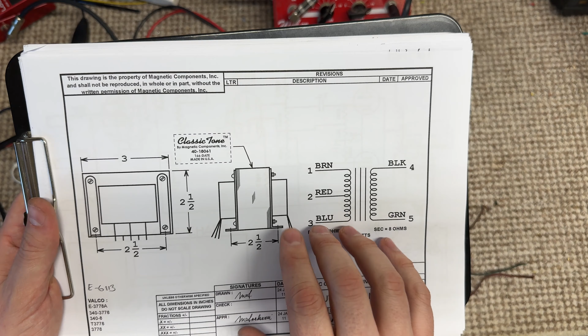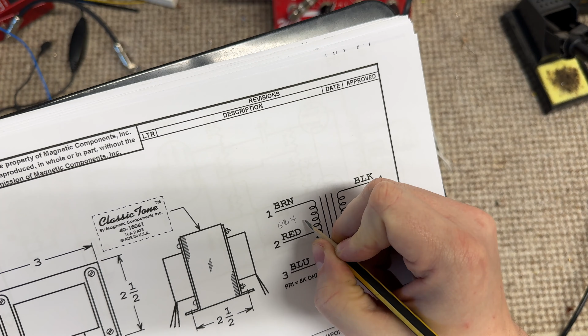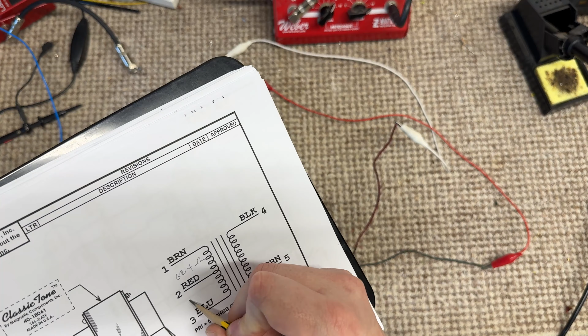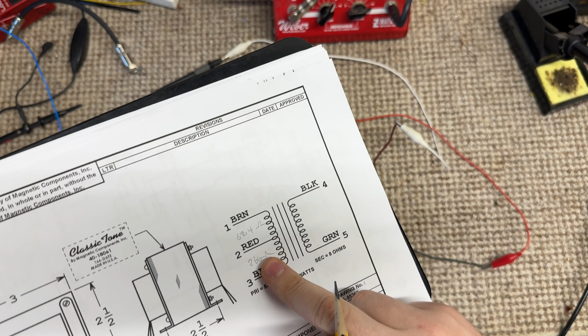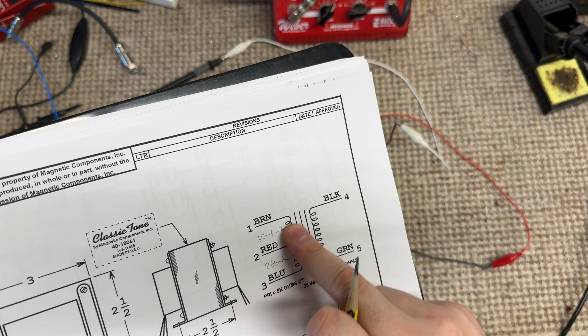Before that, we'll just measure the DC resistances of the windings. Going from red to brown on this side - pencil's knackered - what have we got? 62.4 ohms. Now moving from brown to blue, we get 266 ohms. They should be roughly the same across each side, so yeah, I think we've got an issue there, don't you? Just to confirm, if I go from center tap across the entire winding, we get 328. That is not a healthy transformer - don't need to take it any further than that. She is knackered.